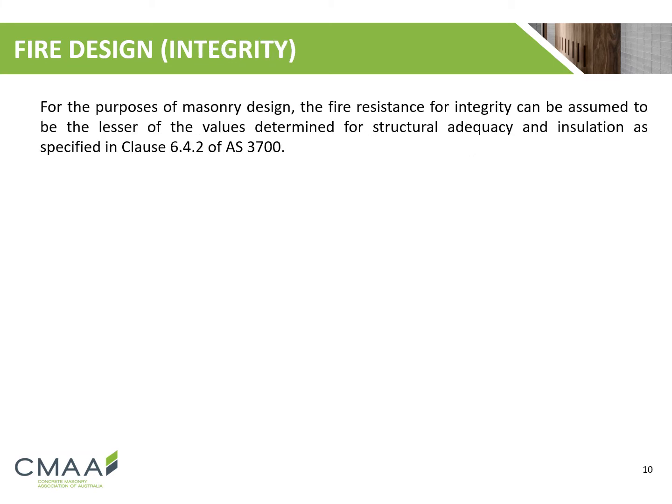For the purposes of masonry design, the fire resistance period for integrity can be assumed to be the lesser of the values determined for structural adequacy and insulation. This is specified in clause 6.4.2 of AS 3700.